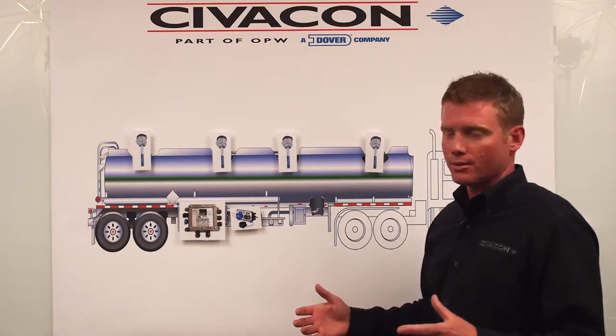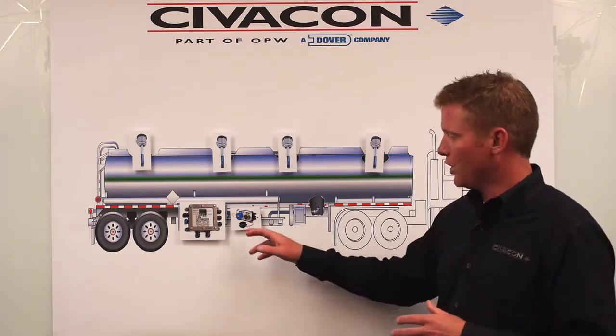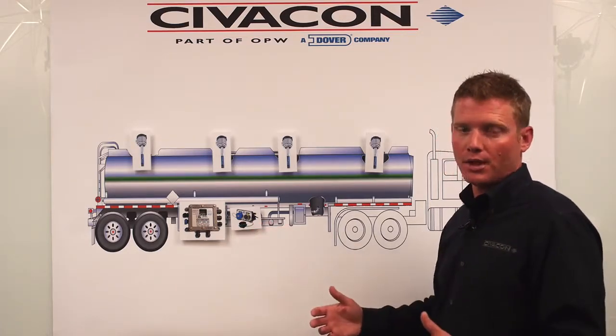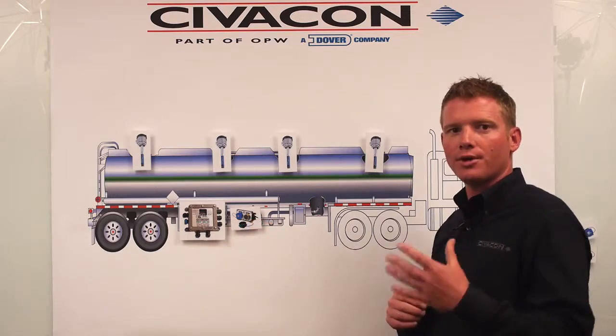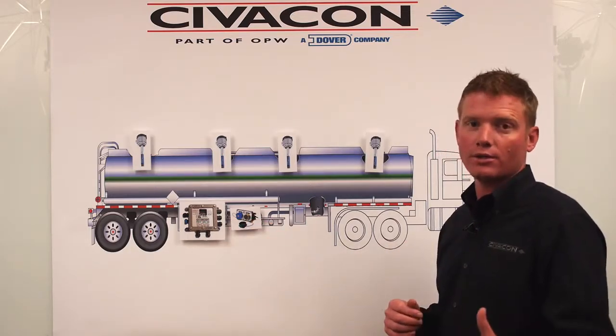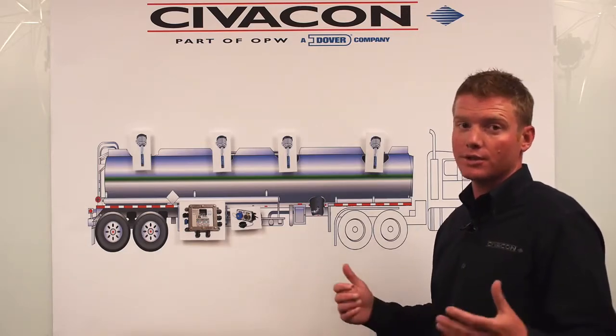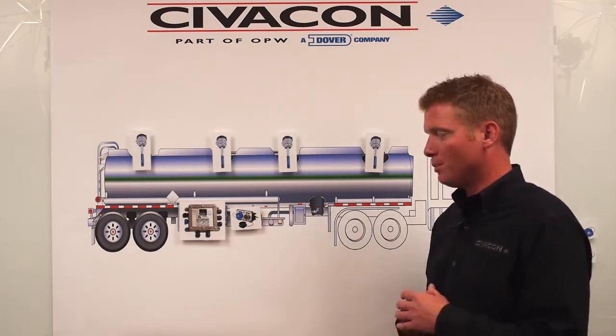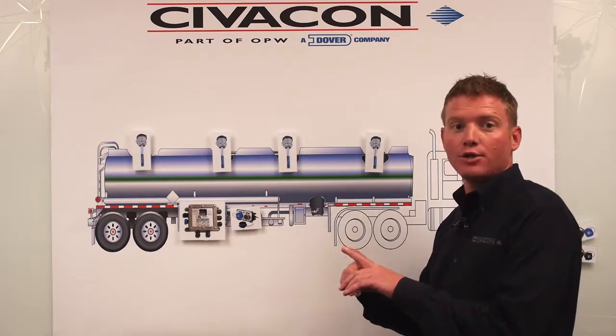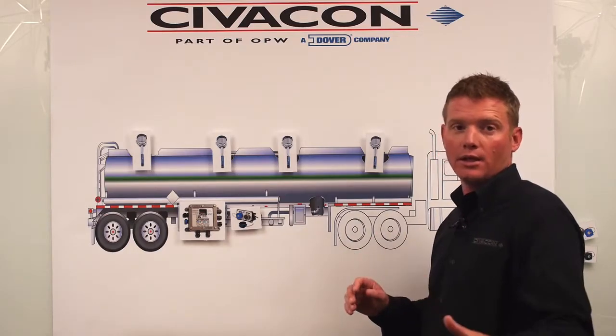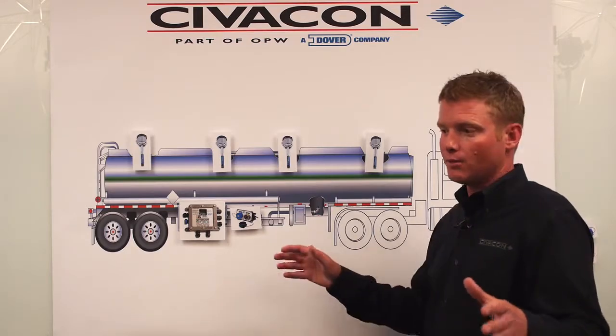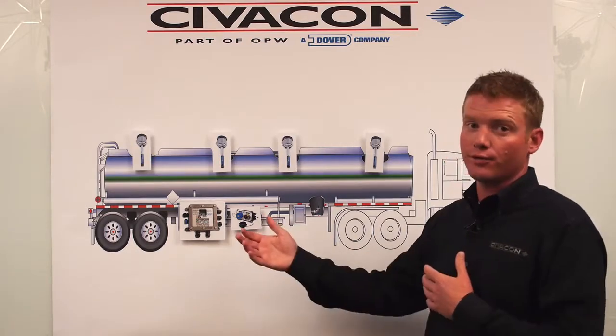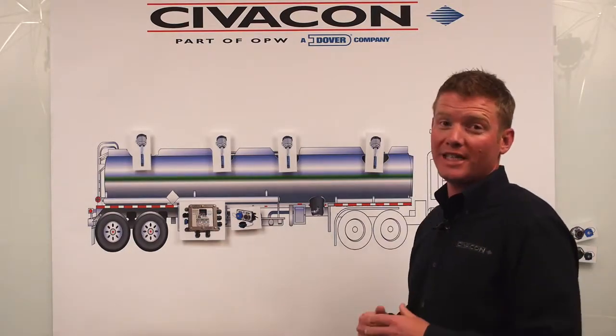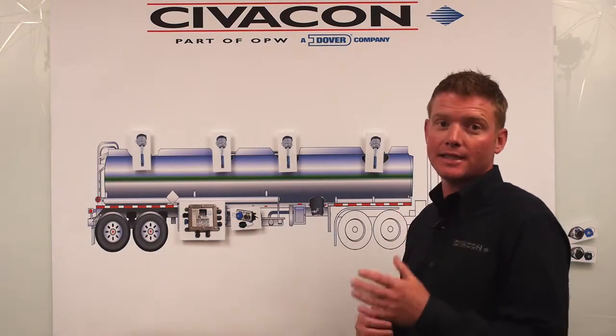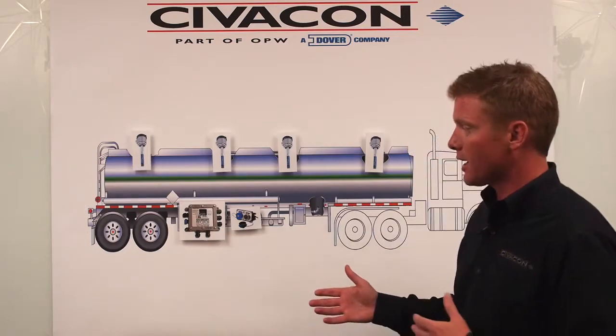So when you get to the loading terminal, really the loading terminal is determining which one you need, the optic or the thermistor plug. It's really how it's keyed, and the loading terminal is really going to have one. So whatever color plug they have at the loading terminal, let's just say it's blue, that's going to be the socket you plug into, and that's a communication link saying your overfill is working. The rack monitor sees that communication, and when they agree, they give you the permit and you're ready to load fuel. So 2 wires are most common on the eastern part of the United States, typically east of the Colorado Rockies. If you're east of the Colorado Rockies, the chances are you have a 2-wire overfill system.